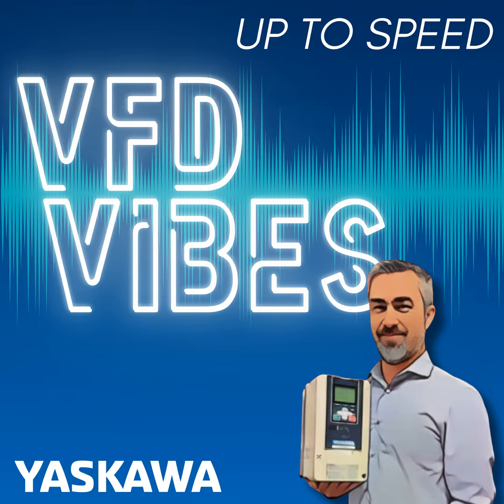And aside from needing to set accel, decel to be able to physically match the requirements of the application, I would imagine that a nice controlled acceleration, deceleration, it has to be good for the longevity of the equipment as well, right? Sure. Yeah. So in the old days, let's say 20 years ago, when we're starting across the line, we're getting lights dimming. We're probably squealing belts. We're putting a lot of torque and force on bearings and housings, belt deflection. Rubber mounts are probably getting torqued. A whole bunch of stuff is happening. And then obnoxious noise coming out of the ductwork from 0 to 100%. Now with the VFD, we can ramp it up at a slow speed, and it's much easier on every aspect of the application.